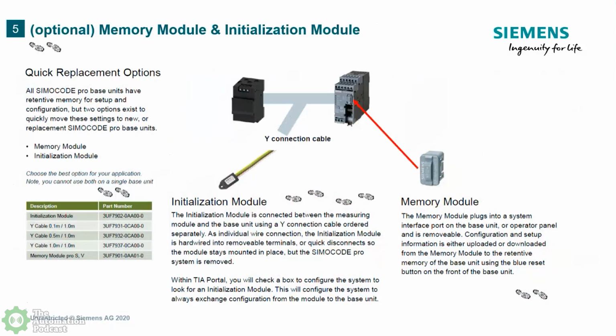But it needs to be programmed. So we have the 2 things you see in front of me. We've got a little memory module that holds the configuration in it where you would plug in. Once you're done swapping it out, cycle the power, and then the memory module sees that there is no configuration inside of it, so it dumps the configuration that it has in the memory module, and you're up and running.